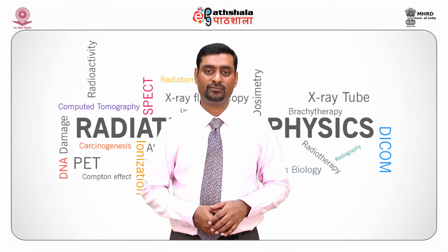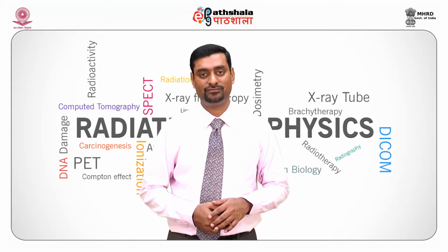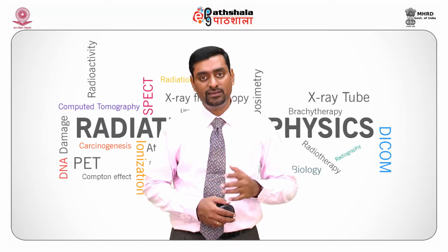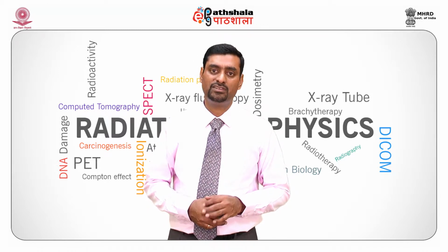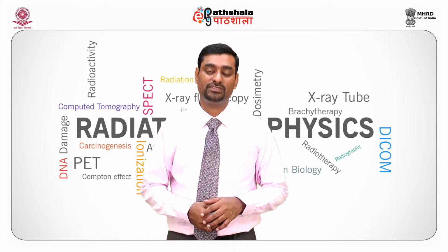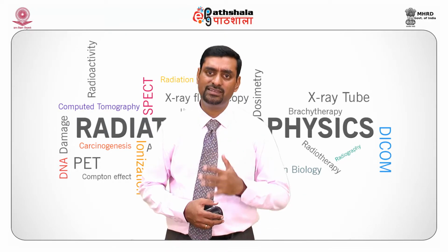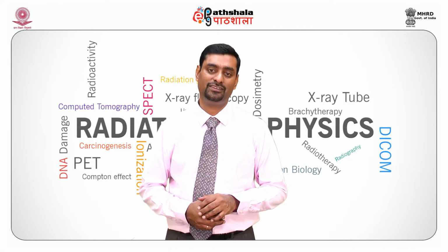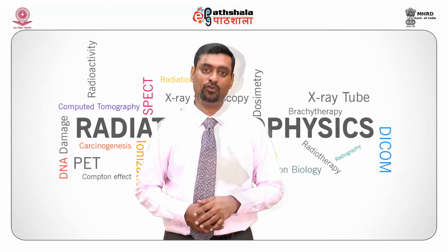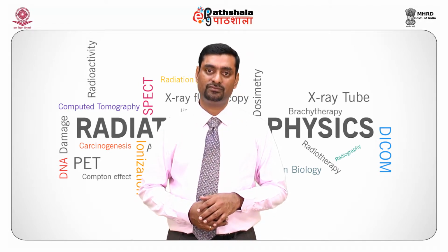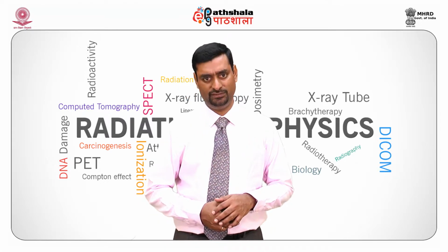Slice thickness. If I go for very thin slice thickness, it increases noise. So generally these days we have high-end CT machines with very small detector size, about 0.5 or 0.625 millimeter in a multi-detector CT. If we take a thin slice as small as 0.6 millimeter, the image is a little noisy. Hence we tend to increase the radiation dose, so the signal is increased and we get better image resolution. So it plays a role in CT.